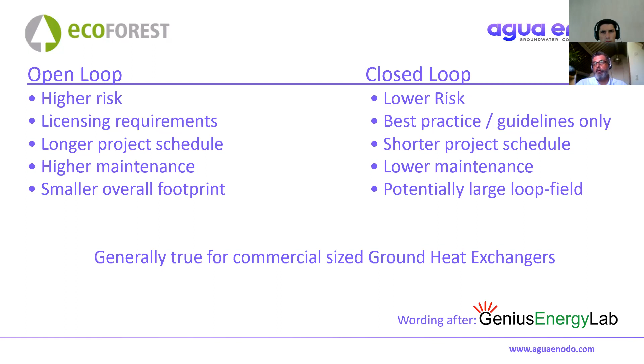When we're dealing with raw water directly from the environment, changing its temperature and potentially its pressure as we pump it, this can cause dissolution and precipitation reactions with that raw water. Therefore there tends to be maintenance required on the plate heat exchangers and on the submersible pump that would be in the borehole. All these things dealing with the environment obviously have a higher implication for maintenance.